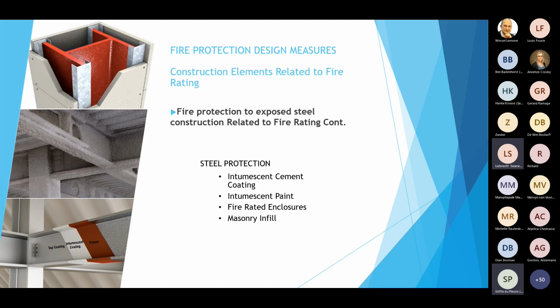Okay, some other construction elements related to fire rating. We've discussed fire doors, we've discussed fire walls, but obviously exposed steel in a building also needs to be protected. Steel without protection doesn't give you any fire rating at all. So on these images, you'll see that the steel beams have been covered with a type of product, what we are calling intumescent cement coating or intumescent paint. That product can be applied by spraying it on, painting it on, or protecting it, as in the top image, with drywalling compartmentalized all around the beam. So there are different ways of doing it, but it's only mentioned for areas where there's no protection and where your steel beams are exposed.